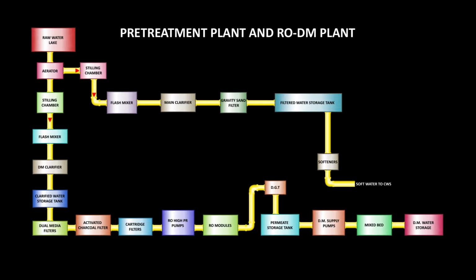In Thermal Power Station 2 expansion, stormwater from mines is treated in pre-treatment plant to produce clarified water and is made to pass through the main clarifier water. Then it passes through the gravity sand filter and softeners, which are used for circulating water makeup. The DM clarifier water is pumped to the RO plant through the dual media filter, activated charcoal filter and cartridge filters to produce permeate water. Then the permeate water passes through mixed bed to produce DM water.